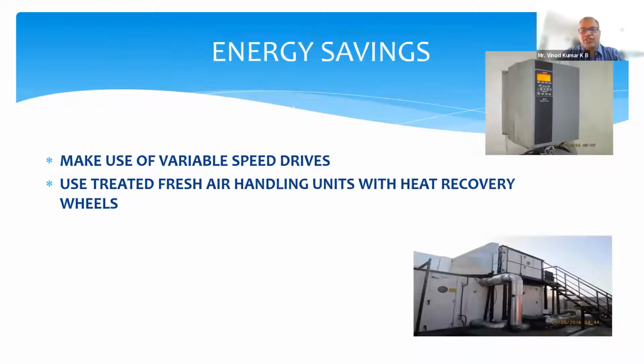Another important point is the use of variable speed drives, because the air handlers for operation theaters or ICUs are generally not to be switched off. They need to be running at all points of time. So to maintain temperature, pressure and humidity control inside the theaters or ICUs, you need to keep the AHUs running. But you need to still save some energy.